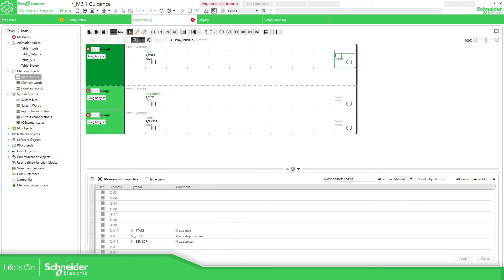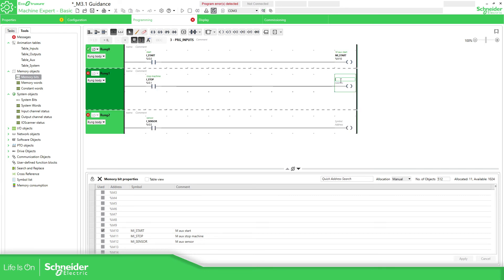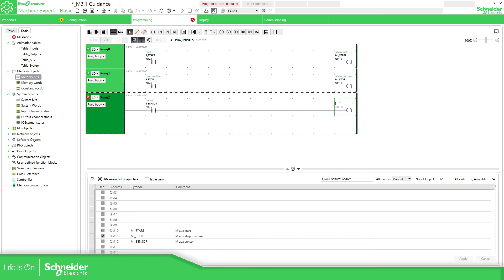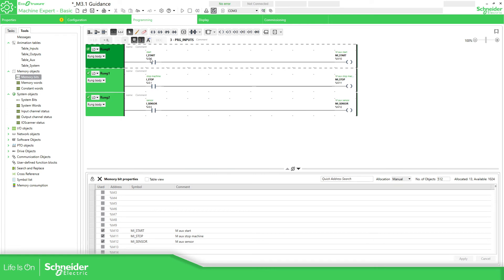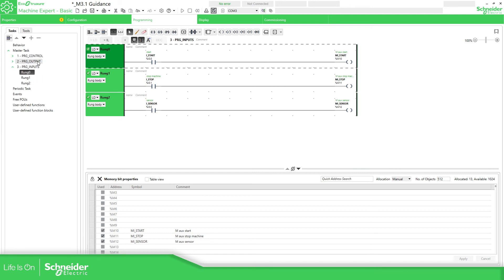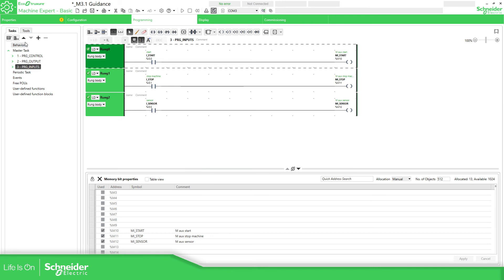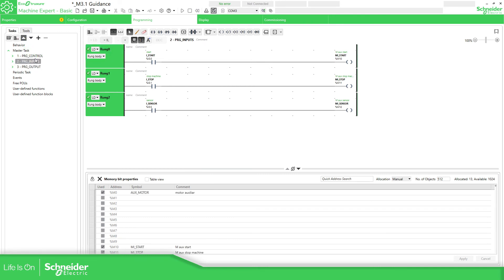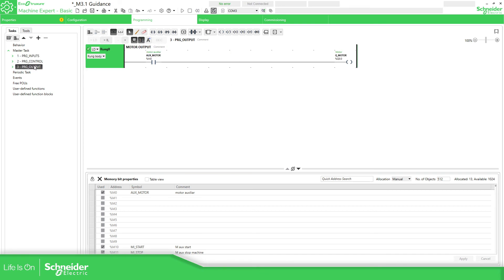So this one will be mi_start, mi_stop and the last one will be mi_sensor. So this way we have moved all the values, the digital values into %m variables. The next step would be to change in our logic, in the control logic, the i for the mi. And there is something important here, which is the order. So the input should be called at the beginning, OK, because in the PLC the cycle is input, execute the code and then refresh the output. So input first, control and then the output.